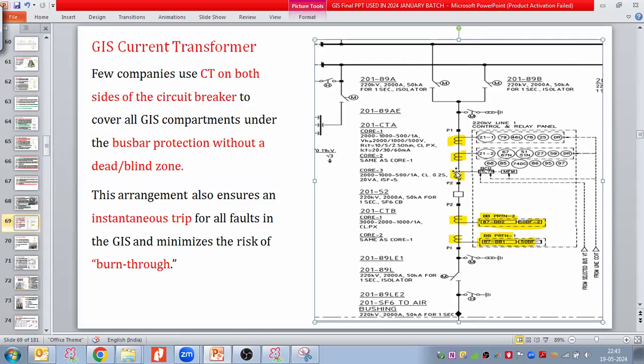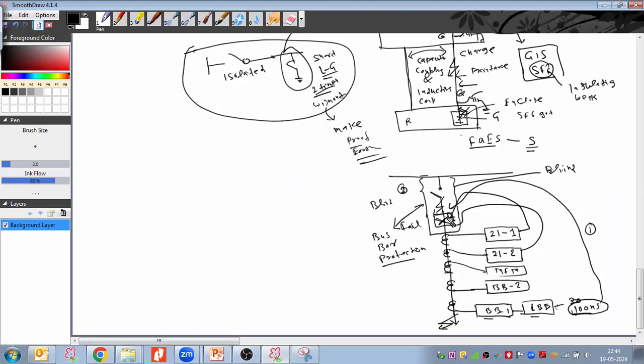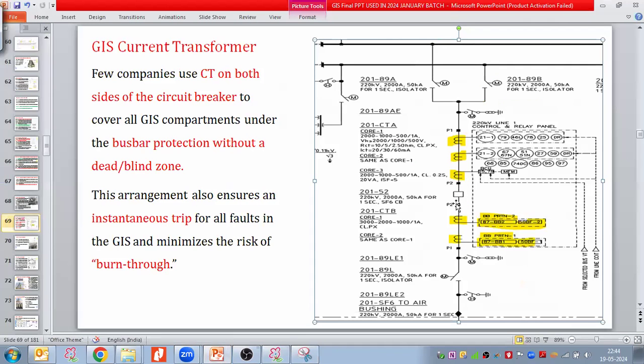This CT is going to sense the current, right? If you are not putting the CT here, you are not going to sense the current unless you close the circuit breaker. So distributing the CTs on both sides of the breaker is an added advantage. Even though your cost increases, you are getting a higher service life. Earlier in this arrangement, the breaker was under the bus bar protection zone. But in this protection scheme, any fault in the breaker will be covered under your line protection.